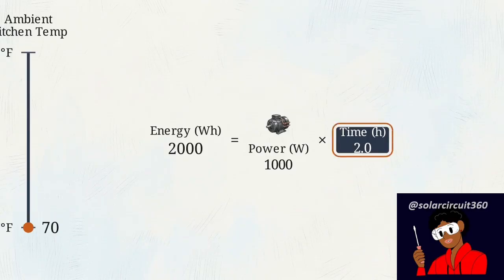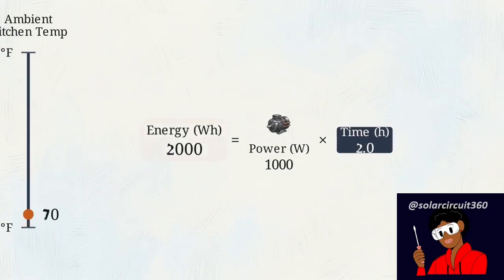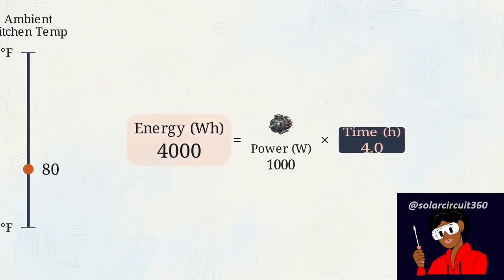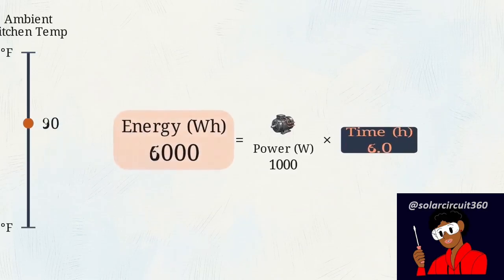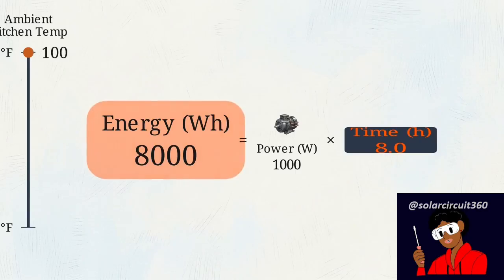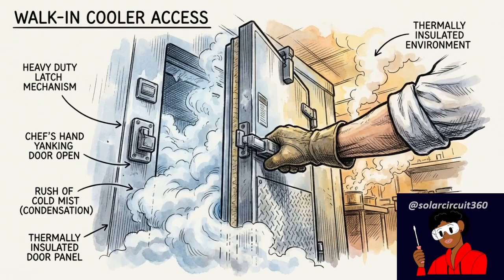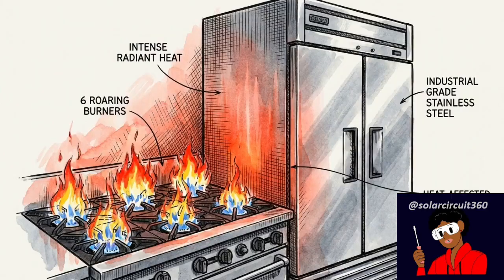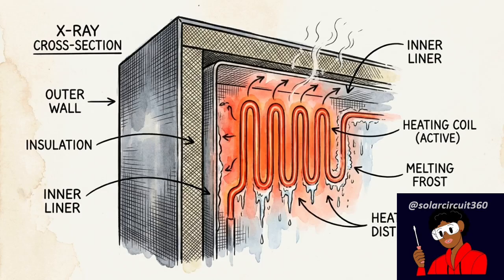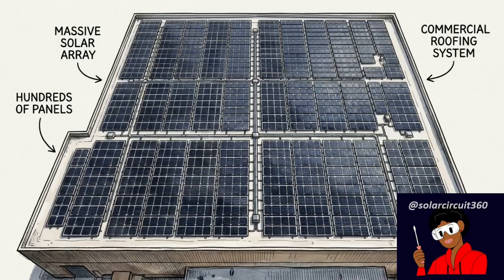Watch the time multiplier on this equation. As ambient temperature slides upward, the internal environment fights the refrigeration. The compressor runtime physically expands, forcing the total watt-hour consumption to rise significantly. Add in the constant door openings by the prep staff, proximity to the hot cooking line, and hidden internal defrost heaters, and those compressors are forced into near-continuous operation. This expanded energy load demands heavily oversized solar arrays.